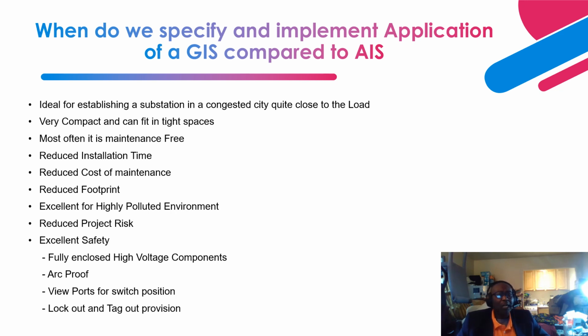And as such, if you have a highly congested city, where space is a premium, it becomes the ideal choice for you to specify a GIS, so that it can fit in tight spaces and blend with the environment. Next, I'll say that most often it is maintenance free. That is the slogan that the manufacturers will tell you, and it is partially true, or quite close to the truth. But it all depends on the first 10 to 12 years, how you operate, how you follow the manufacturer's instructions to operate the GIS to achieve that maintenance-free slogan that they are indicating.